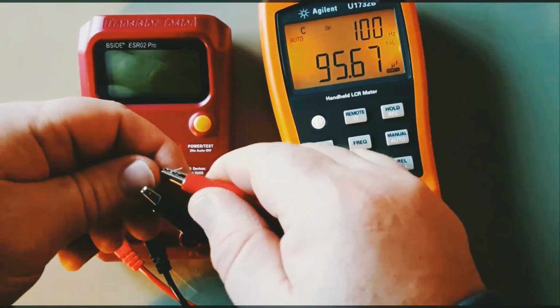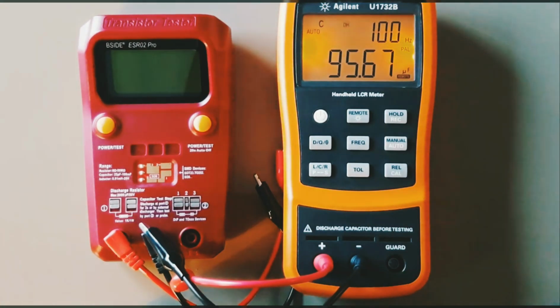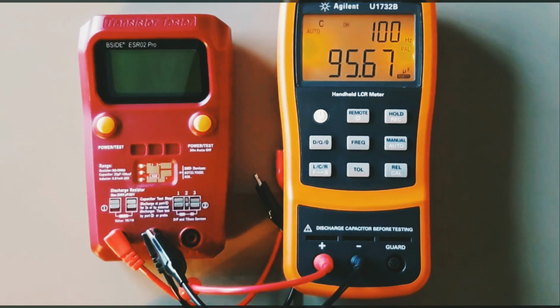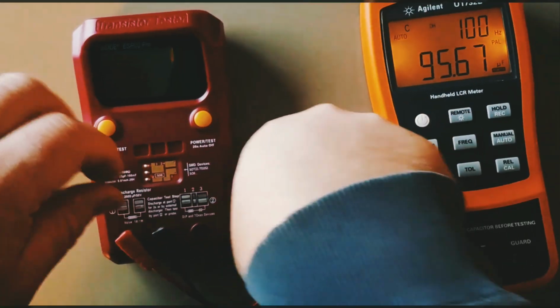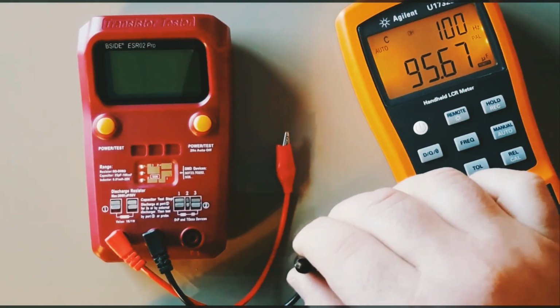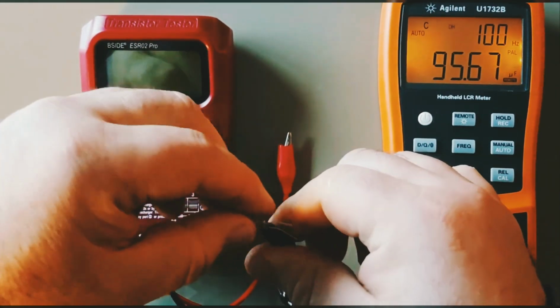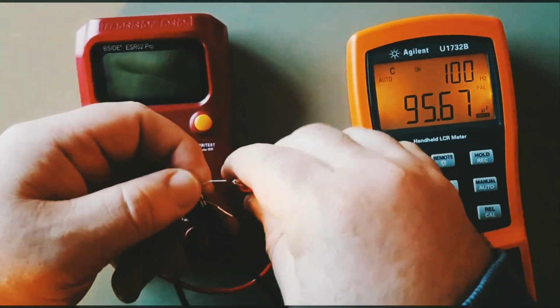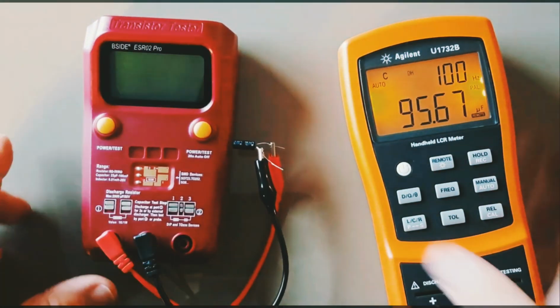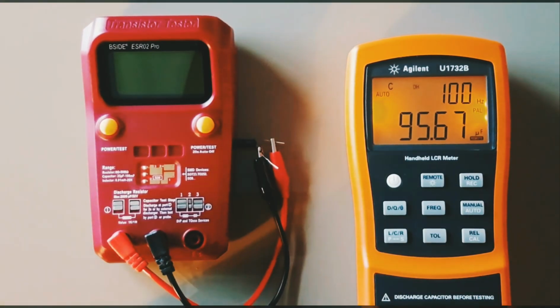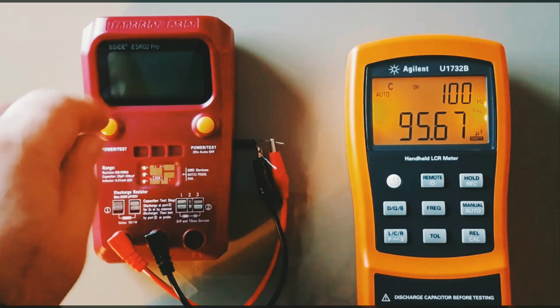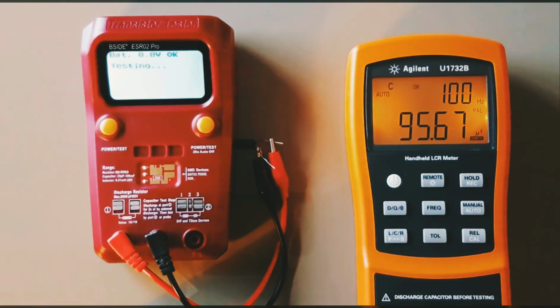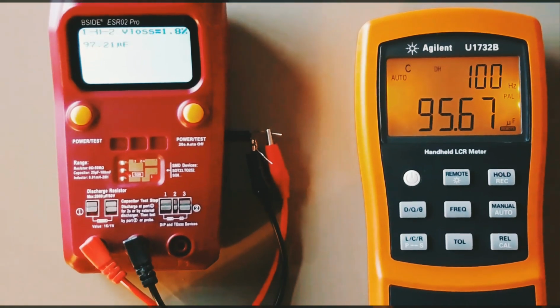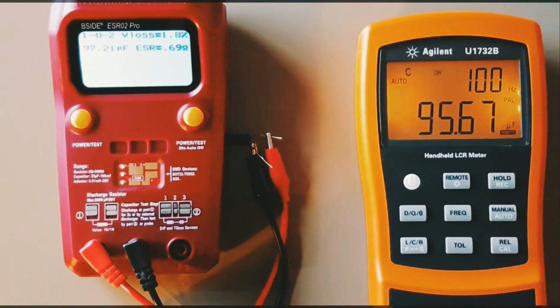Okay, so what we'll do now is we'll take that off and we will hook it up to the B-side. And we'll just see how close they are. Apologize, it's a little bit awkward seeing my big hands in front of the screen, but bear with me. Now to turn on the B-side, you can use either the left or the right button. And there we go. Testing. And the B-side is showing us a 97.21. So in comparison, they're pretty well spot on.